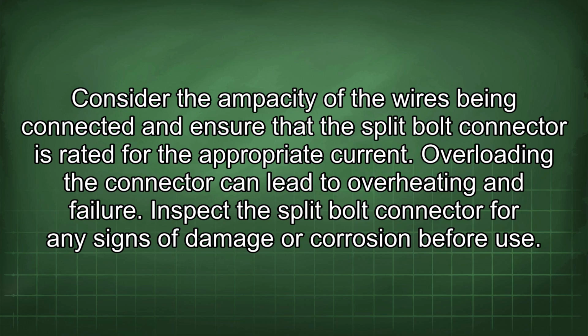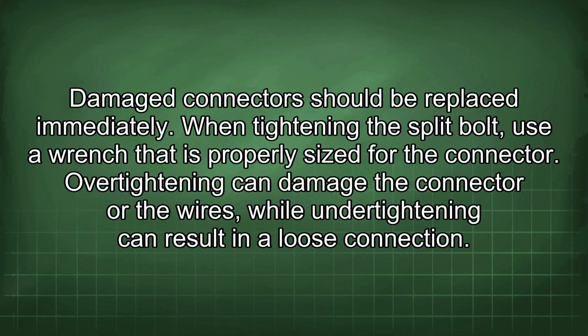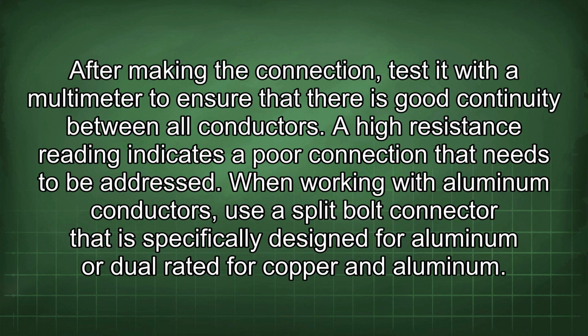Inspect the split bolt connector for any signs of damage or corrosion before use. Damaged connectors should be replaced immediately. When tightening the split bolts, use a wrench that is properly sized for the connector. Over-tightening can damage the connector or the wires, while under-tightening can result in a loose connection. After making the connection, test it with a multimeter to ensure that there is good continuity between all conductors. A high resistance reading indicates a poor connection that needs to be addressed.